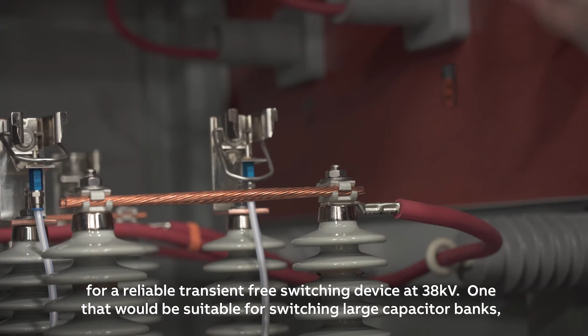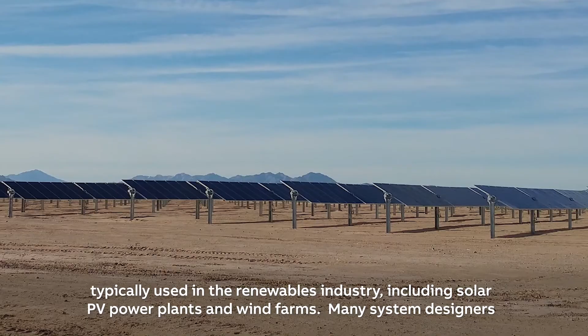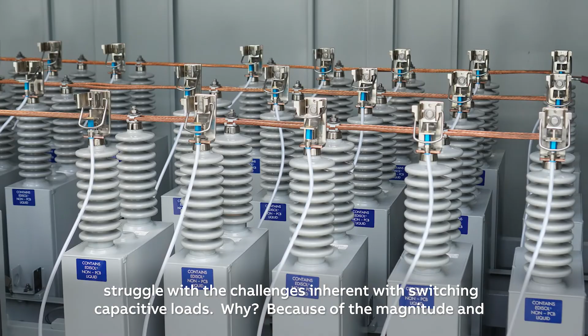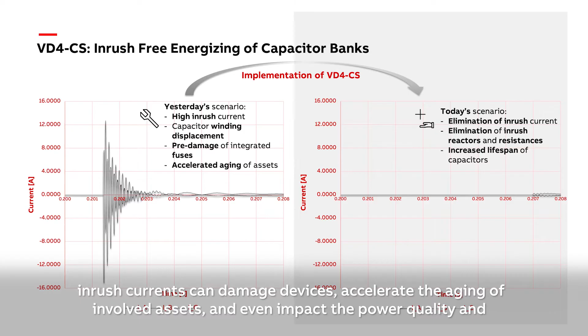One that would be suitable for switching large capacitor banks typically used in the renewables industry, including solar PV power plants and wind farms. Many system designers struggle with the challenges inherent with switching capacitive loads. Why? Because of the magnitude and frequency of the inrush currents involved and the requirement for reliable, restrike-free switching for frequent operations that exceed the ratings of standard medium voltage distribution circuit breakers. In some cases, these inrush currents can damage devices, accelerate the aging of the involved assets, and even impact the power quality and reliability of the network.